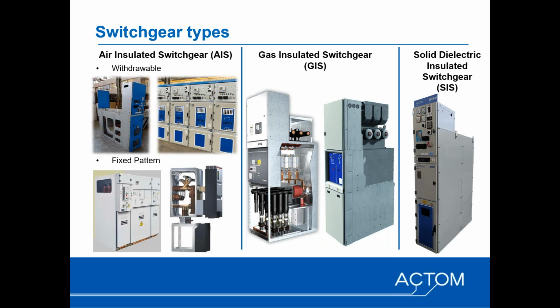But on the left, we've got AIS or air insulated switchgear. And again, although the dominant format or architecture is of the withdrawable pattern, you do also get air-insulated fixed pattern switchgear, as shown in the bottom example. So it's not necessarily always withdrawable.